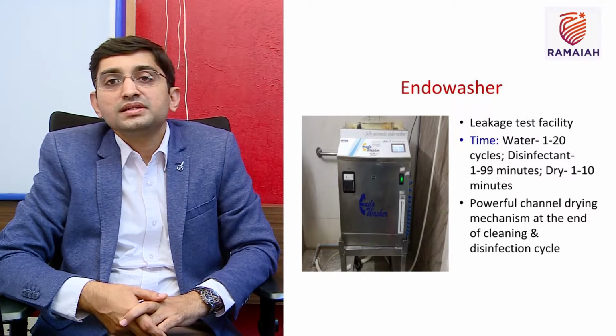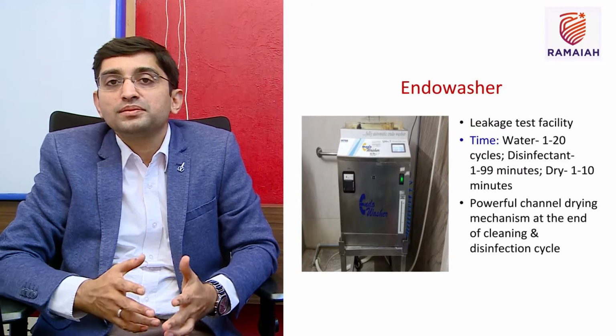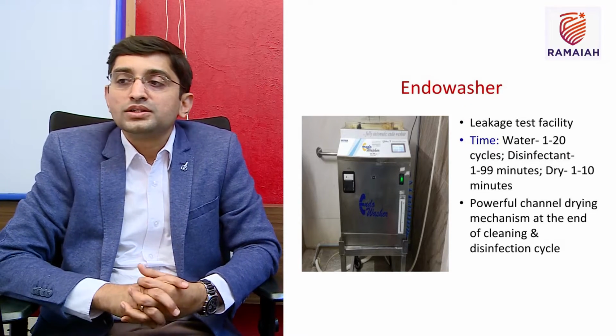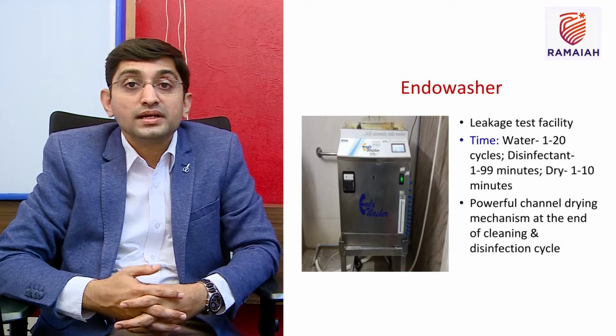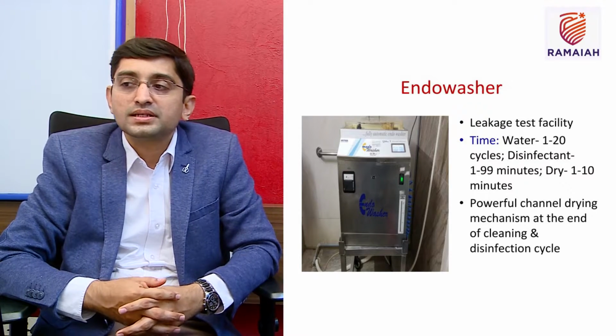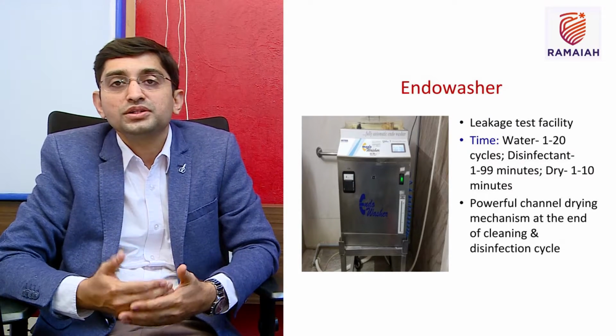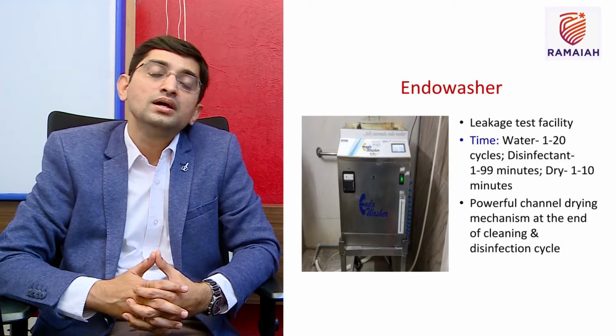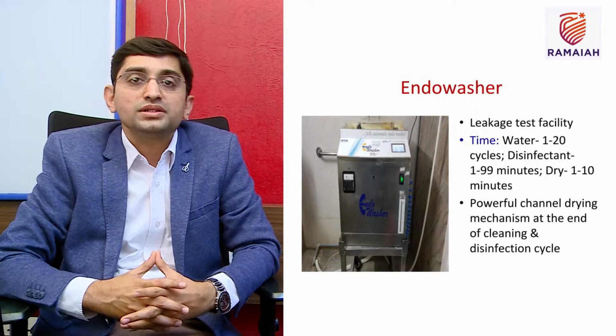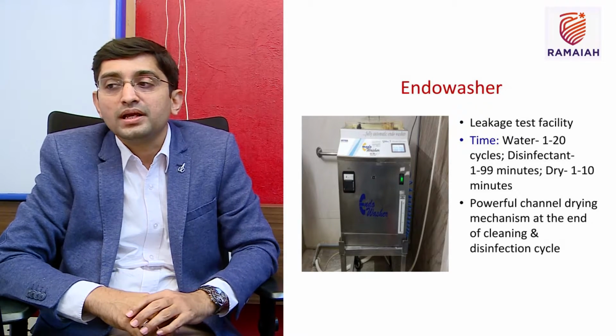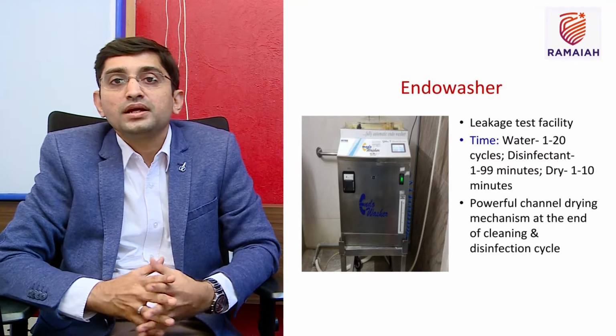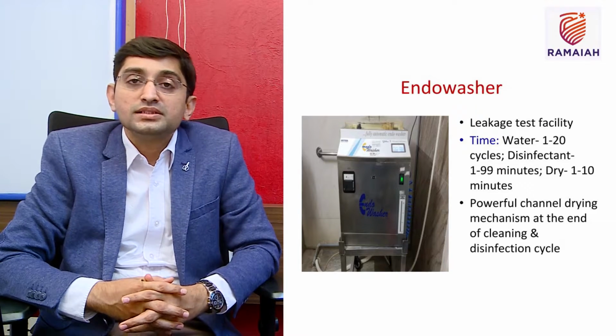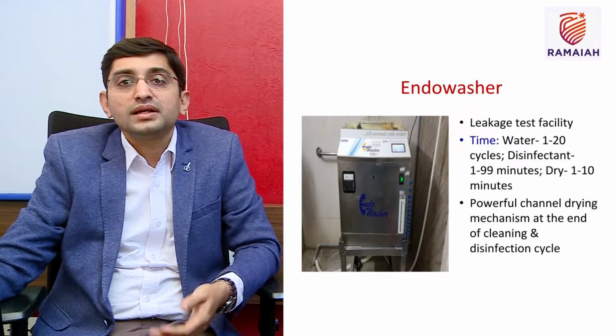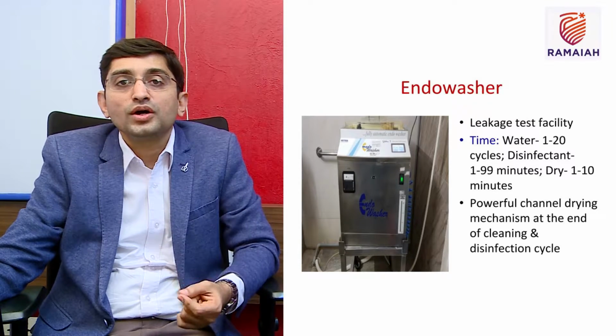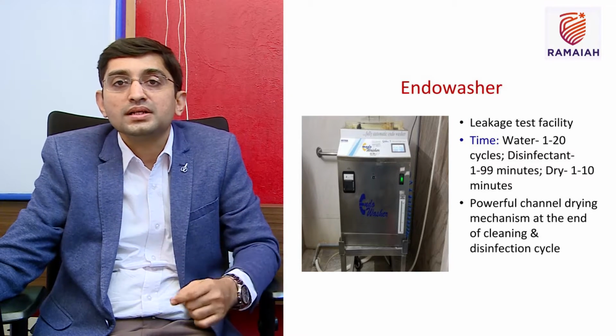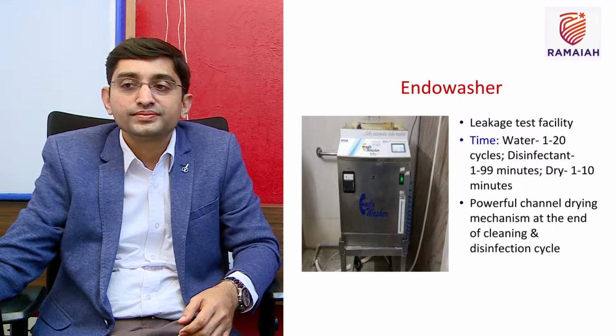The advantage is we can set the time and how much water, similar to our washing machine. This is a washing machine for the endoscope, so we can set how much water and how many cycles it needs, like 1 to 20 cycles. For disinfectant also, how much disinfection you want, like 1 to 99 minutes can be set. After that, the advantage of the endo washer is it can dry the scope by putting in air. The dryness can be adjusted by approximately 1 to 10 minutes. There is a powerful channel drying mechanism, because at the end, if the scopes are not dry, water can sediment within the biopsy port, and then accessories passing freely can be a problem.